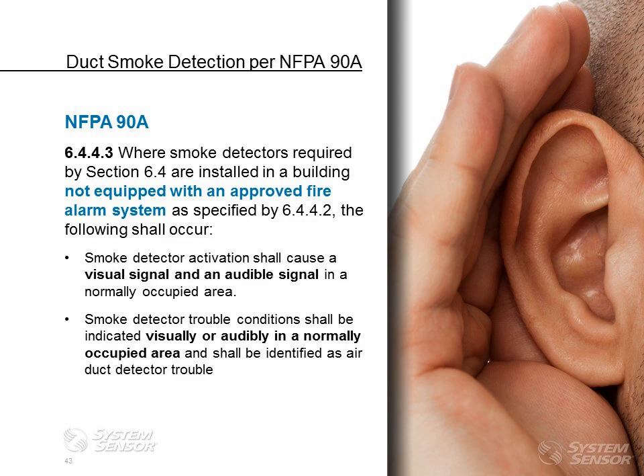Continuing with 90A, where smoke detectors required by Section 6.4 are installed in a building not equipped with an approved fire alarm system, as specified by 6442, the following shall occur. Smoke detector activation shall cause a visual signal and an audible signal in a normally occupied area, and smoke detector trouble conditions shall be indicated visually or audibly in a normally occupied area and shall be identified as air duct detector trouble. A lot of people believe that if there's not a fire alarm system required in the building, they don't have to put duct detectors in. That's not the case. You still have to put the duct detector in, and you still have to put the remote annunciation or remote indicator in. That is required, whether there's a fire alarm system or not.